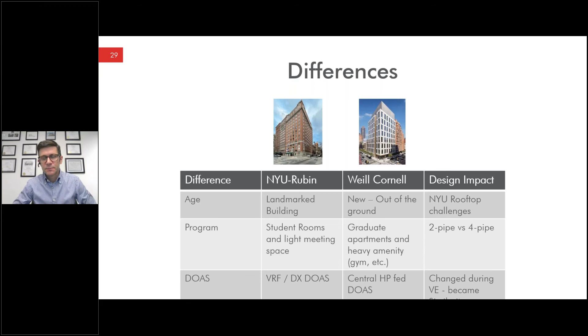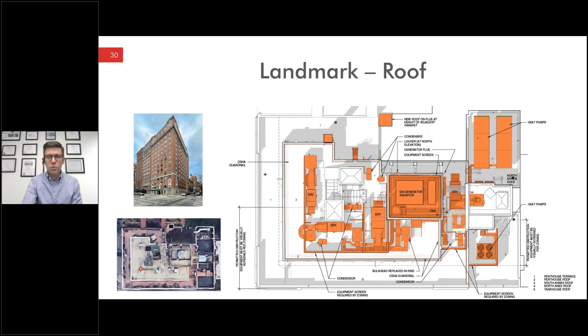Okay, so going on again, the roof was a very complicated solution at NYU. One thing to note is the acoustics became a challenge here in addition to just space. The acoustics of the heat pumps was something that we had to deal with, as this building is located pretty close to a neighbor just to the north. So we did have to go through that with the manufacturer, and the attenuation was definitely a pretty hot topic for a while. So definitely be aware of that if you're next to an existing building. It is going to be a lot harder than cooling towers, as you might expect.